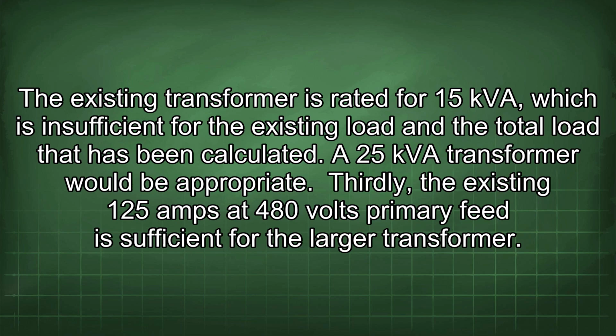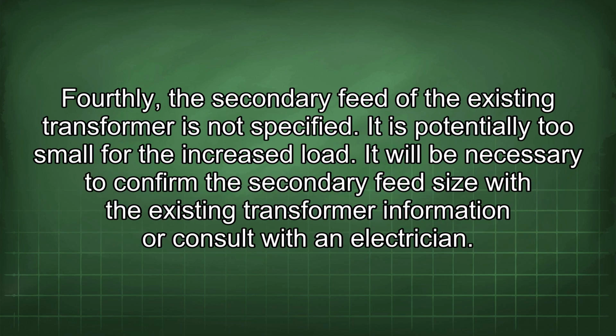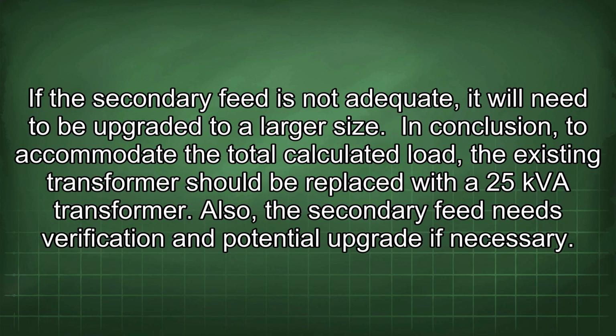Thirdly, the existing 125 amps at 480 volts primary feed is sufficient for the larger transformer. Fourthly, the secondary feed of the existing transformer is not specified. It is potentially too small for the increased load. It will be necessary to confirm the secondary feed size with the existing transformer information or consult with an electrician. If the secondary feed is not adequate, it will need to be upgraded to a larger size.